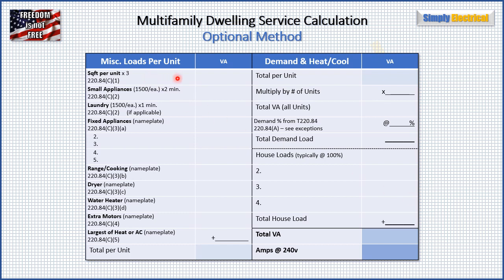We're going to start in the left-hand column. We take the square footage of each unit times three to get a VA value. Then we take the small appliance loads, laundry loads if they apply, and fixed appliances with their nameplate ratings. We take our range or cooking at its nameplate, our dryer at nameplate, water heater at nameplate, and any extra motors at their nameplate. Then we take the largest of the heating or cooling at its nameplate. We tally all these up to get our total per unit VA, then multiply by our number of units to get total building VA. Then we go to table 220.84 and get a demand factor, apply that to get our total demand load.